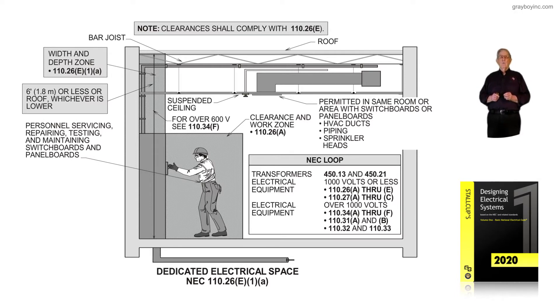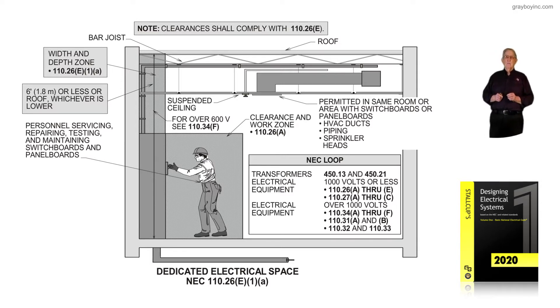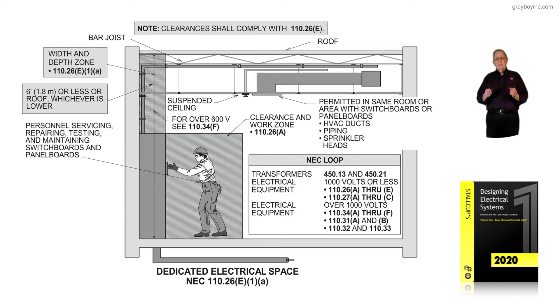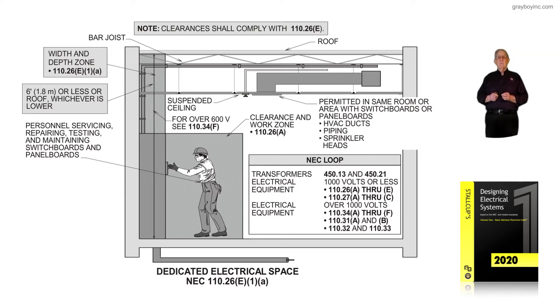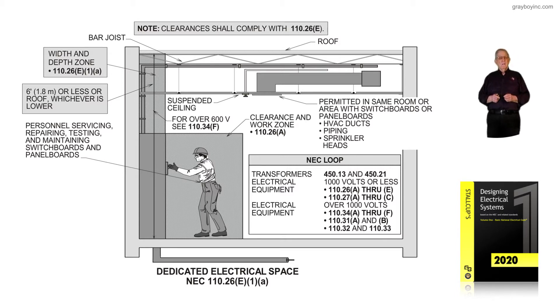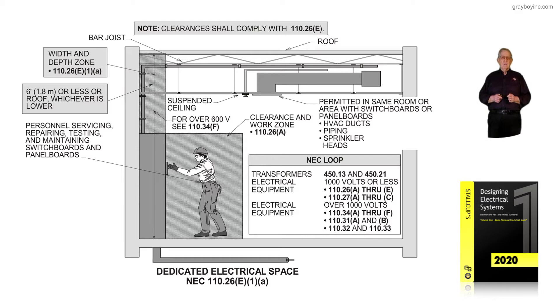Notice again that we show an air conditioning duct coming in that's for that room. We show piping, sprinkler heads and things that are related to the room, and that's okay. Notice that we have the clearance in workspace of 110.26A, and we have the three-foot because condition 1, 2, or 3 is not applicable here because we do not have shown in the illustration a wall behind the worker's back.